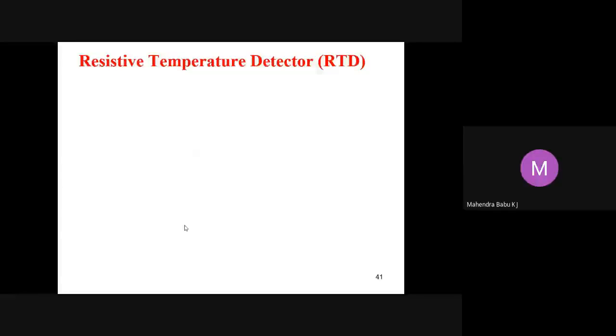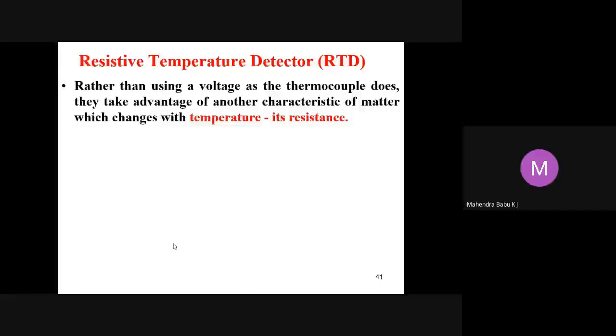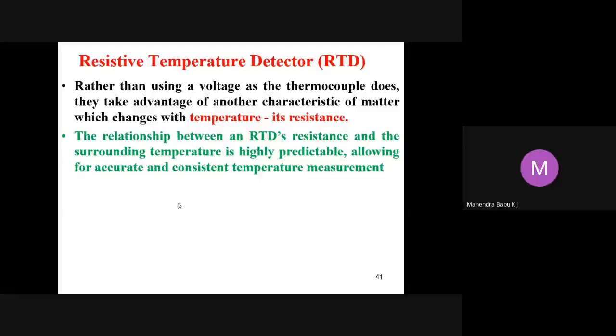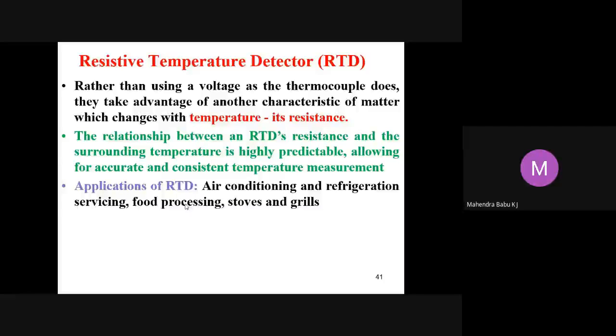Another type of temperature sensor which is normally used is the resistive temperature detector, or simply RTD. So instead of using voltage as a thermocouple does, this takes advantage of another characteristic of matter which changes with temperature, that is resistance. So thermocouple uses the variation of voltage, but here it uses the variation of resistance for measurement of temperature. The relationship between an RTD's resistance and the surrounding temperature is highly predictable, allowing for accurate and consistent temperature measurement. And these RTDs are normally used in air conditioning and refrigeration, servicing, food processing, stoves, and grills.